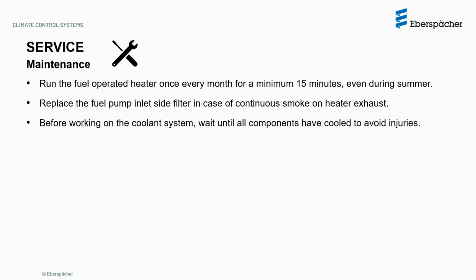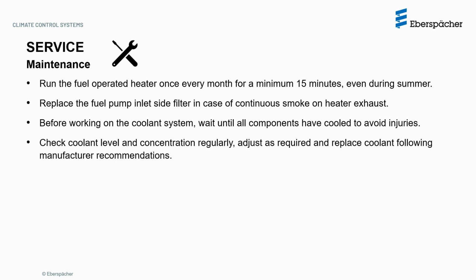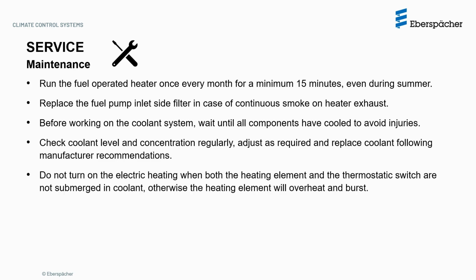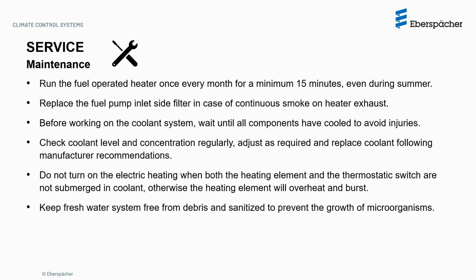Before working on the coolant system, wait until all components have cooled to avoid injuries. Check coolant level and concentration regularly, adjust as required, and replace coolant following manufacturer recommendations. Do not turn on the electrical heating when both the heating element and the thermostat switch are not submerged in coolant. Otherwise, the heating element will overheat and burst. Keep freshwater system free from debris and sanitized to prevent the growth of microorganisms.